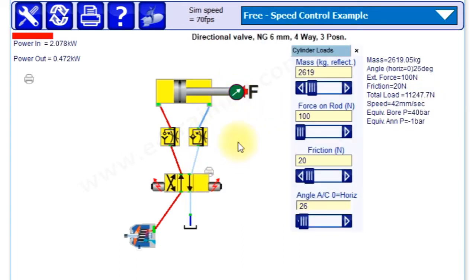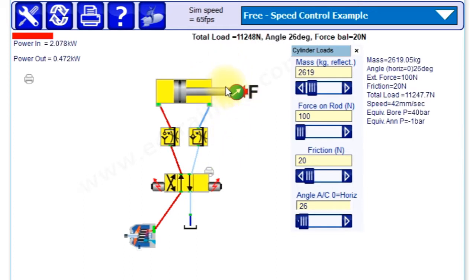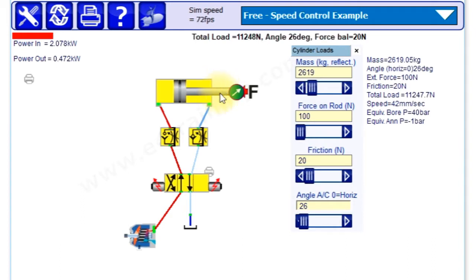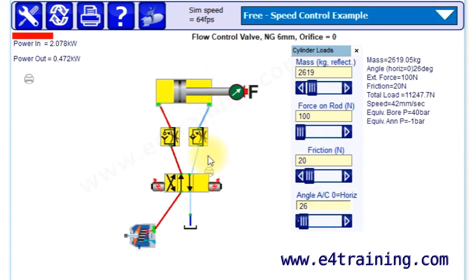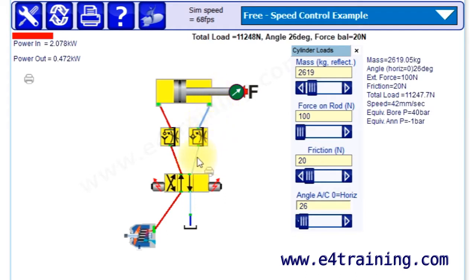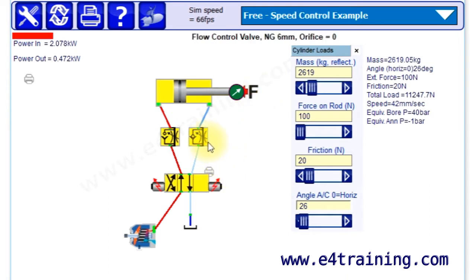That's all there is to it really. It does get quite complicated to think about - you have to know your loads. As I said before, the most important thing is your load and how your load's changing over time. Each time that load changes, the pressure drop and the speed of operation changes as well. There are pressure compensated valves where that doesn't happen, but we'll get to those later.